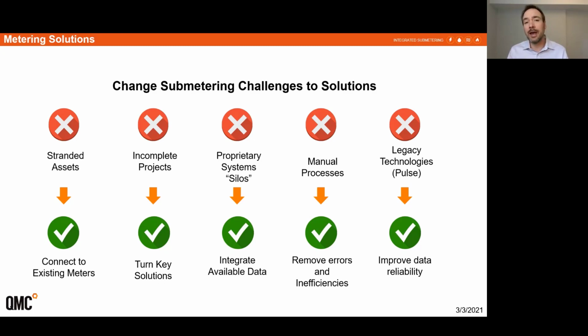We've written code to get that meter data out of them and then into a more open protocol format to pass that data on to other groups. Manual processes, so manually going and reading meters, is fraught with challenges. You have meter data entry failure and human error. And most importantly, you're also losing all the good data in the meter, like interval data. So what we do is either access those manual read meters or replace them with digital meters so we can get interval data out and do the energy savings activities that we're discussing today.